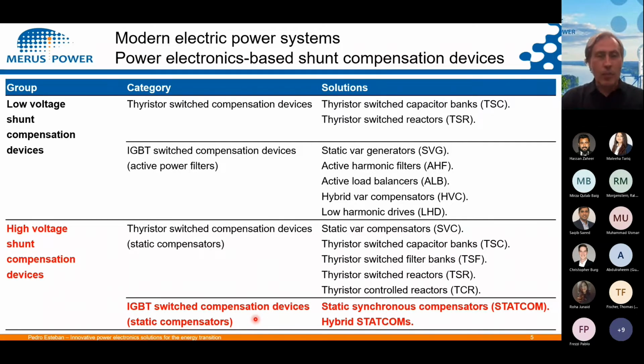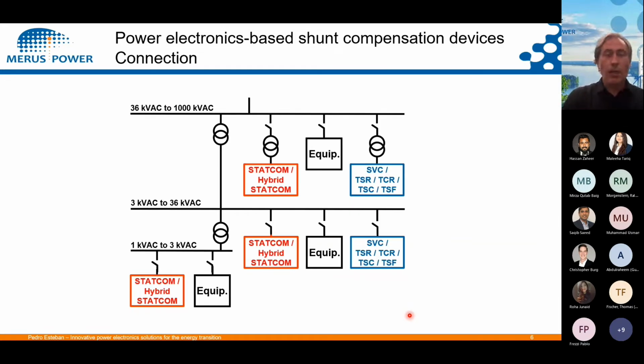Also, they can be called static compensators. Two types: STATCOMs and hybrid STATCOMs. These devices are pretty flexible, because here you can see how we can connect them in the high voltage electric power system. Depending, of course, on the manufacturer and the design, they can be connected directly in this voltage range. If we use IGBTs of 2 kilovolts, 3 kilovolts, we can also connect them directly up to 36 kV, or we can connect them with a step-up transformer to almost any kind of voltage level.